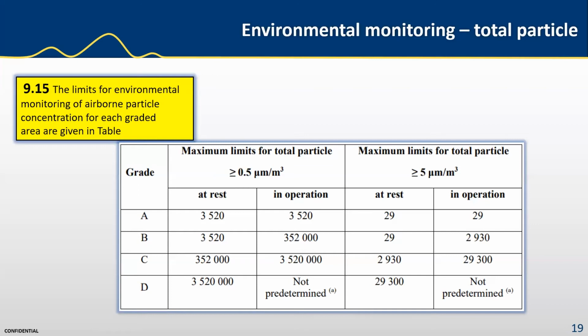And this is an interesting statement, which really directs you towards trending, rather than just following this table and having one event where you have a 1 minute sample, as I outlined earlier. You could have 4 hours of zero counts, one sample in the 1 minute which would exceed the alarm limits here, and then you could have another 4 hours of zero counts. That's not a trend. That's an event, a transient event. So what we're looking for here is trends and failures in the system.